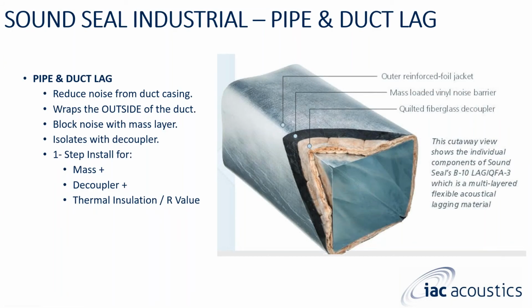Moving on to our pipe and duct lagging material. It is an excellent way of wrapping not only pipe and duct, but also a silencer. When doing so, the outer reinforced foil jacket, along with the mass-loaded vinyl noise barrier, along with the quilted fiberglass decoupler, gives you a great way to quell any type of breakout noise that could be happening within the duct and/or within the silencer.